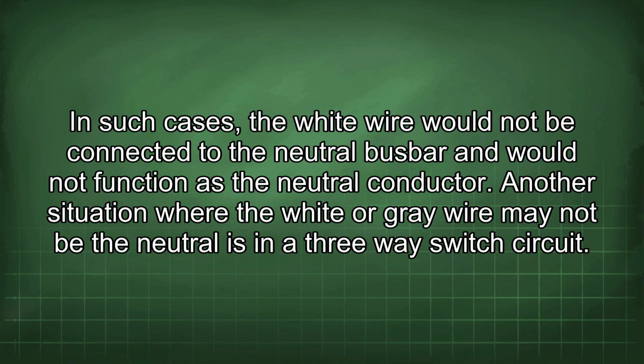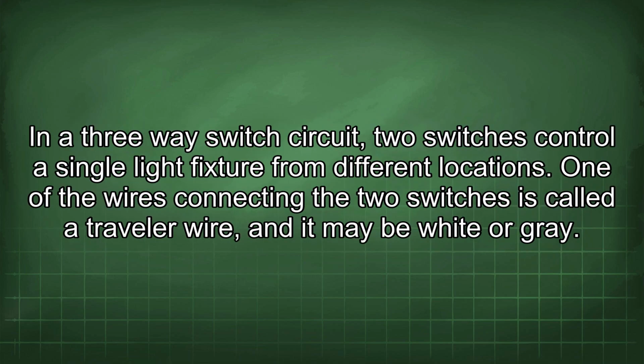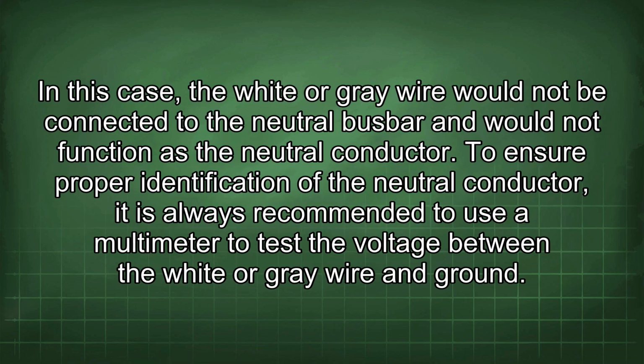Another situation where the white or gray wire may not be the neutral is in a three-way switch circuit. In a three-way switch circuit, two switches control a single light fixture from different locations. One of the wires connecting the two switches is called a traveler wire, and it may be white or gray. In this case, the white or gray wire would not be connected to the neutral busbar and would not function as the neutral conductor. To ensure proper identification of the neutral conductor, it is always recommended to use a multimeter to test the voltage between the white or gray wire and ground.